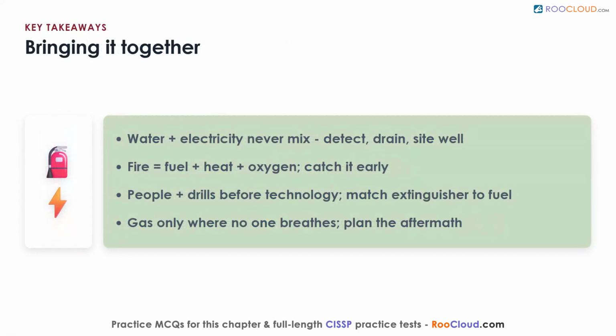So let's bring it together. Water and electricity never mix, so keep systems away from pipes, add detection circuits, and study the site for flooding. Fire needs fuel, heat, and oxygen, and every suppressant removes one, while the four stages reward catching it early. Life safety and trained, drilled people come before any technology. Match the extinguisher class to the fuel, pick detectors and suppression to fit the space, and choose gas only where no one breathes. And plan for the lingering damage from smoke, heat, suppressant, and rescue. Do this well, and the worst physical events stay survivable.